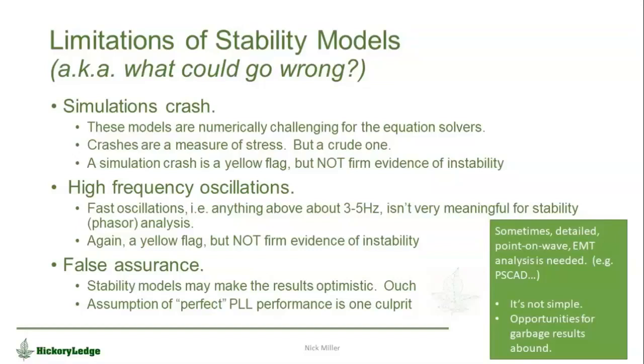Another thing that I see regularly now is the simulation starts to thrash itself, and you get very fast frequency content in the outputs. Well, be really wary of that, because the reality is that programs like PSSE and all of their kin aren't very meaningful for phenomena that are faster than a couple of ones of hertz. They don't capture the bandwidth of controllers at those higher frequencies, and they don't capture the fact that the system impedance as a function of frequency becomes important.